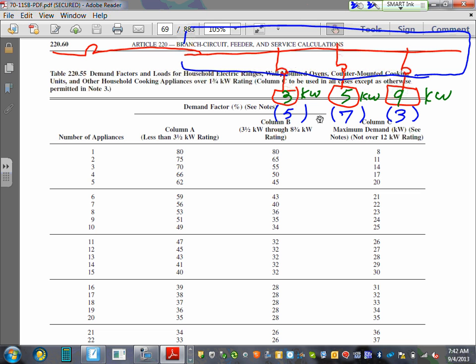You guys have any issues with that? Instead of draw, so how many of them? I don't want to use 2 5s. Let's just use 4 so it can have different numbers. I have 4 of these. So I have 4 ranges, 3 kW each. I have 7 ranges, 5 kW each. And 3 ranges, 9 kW each. And I need to find the demand to size this cable. So what's your job? Your job as a designer is to size this cable and our connection device for this system. And then we'll do the branch circuit as well.